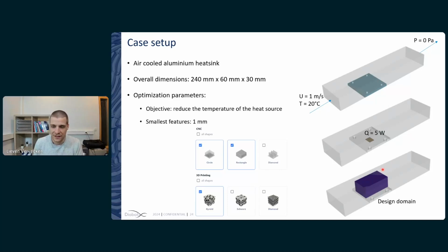You're absolutely right. If there were no bypass, potentially in that scenario, gyroids could be better than pins and fins. The main point was to highlight that TPMS structures are very popular these days, but are not always the best option, the best cooling solution. I hope that this answers your question.